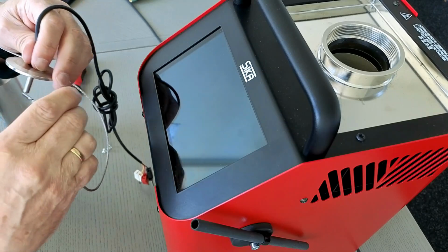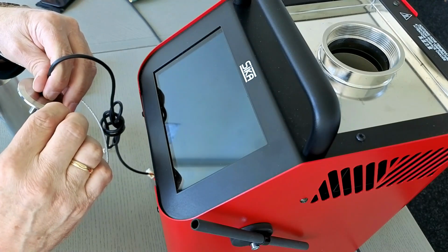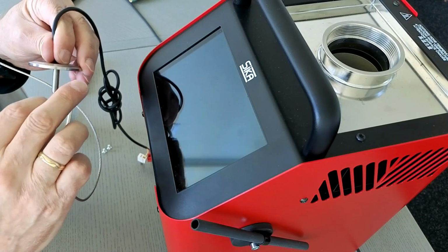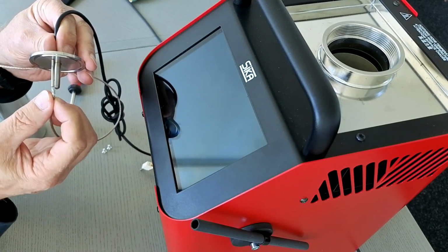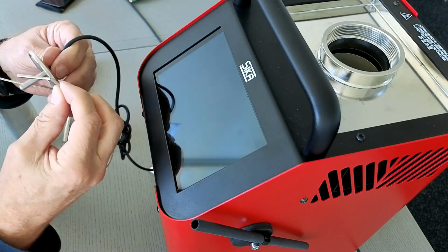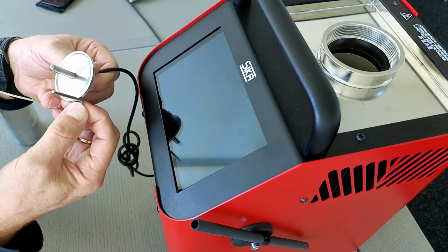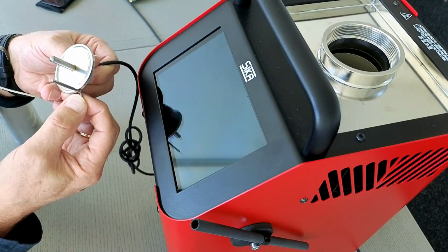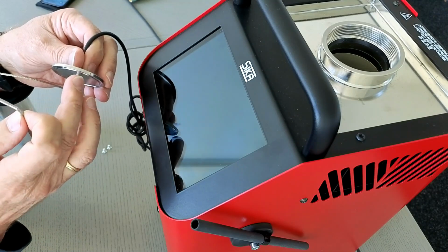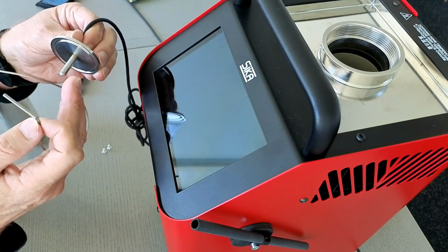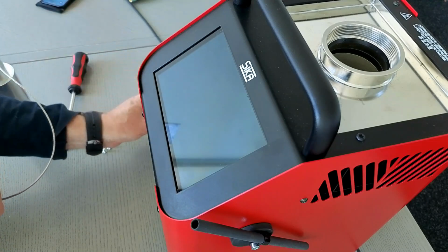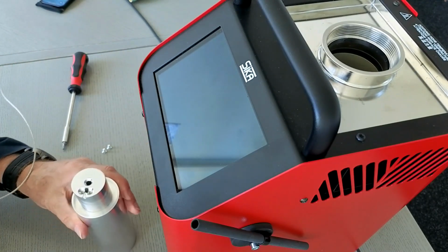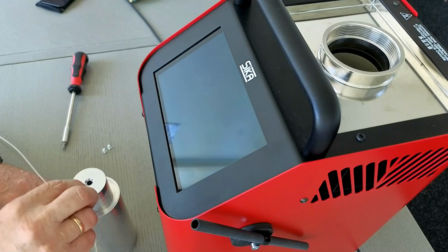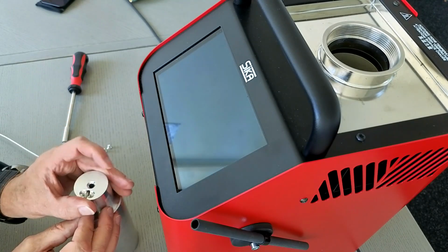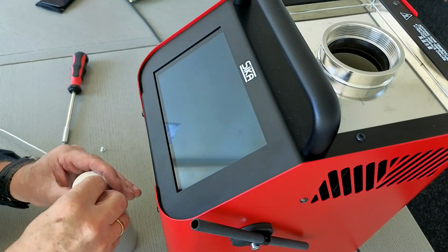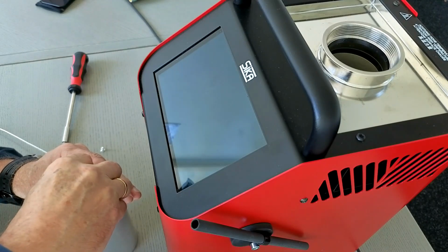You place the reference sensor at the same level as your device under test sensor. This way you can perform a calibration of this kind of sensor with a dry block. So I have the sleeve, I insert the reference sensor cable a little in this direction, then I have fixing screws which I insert.